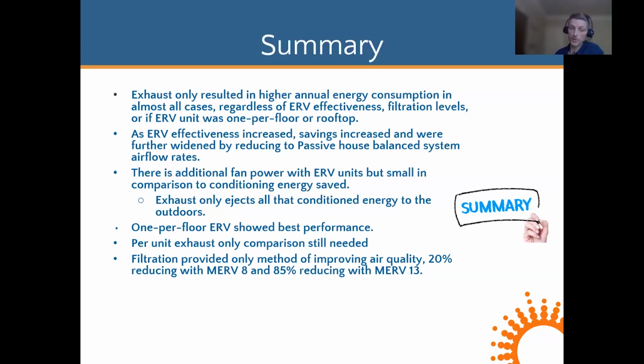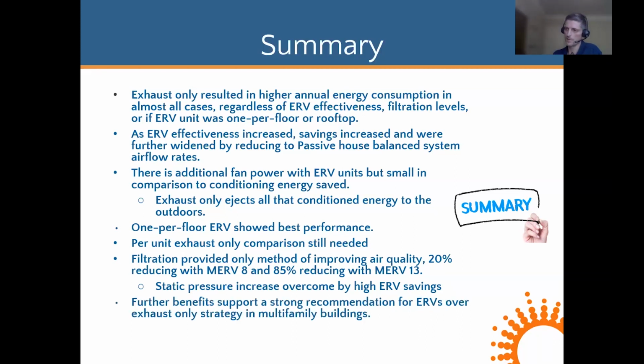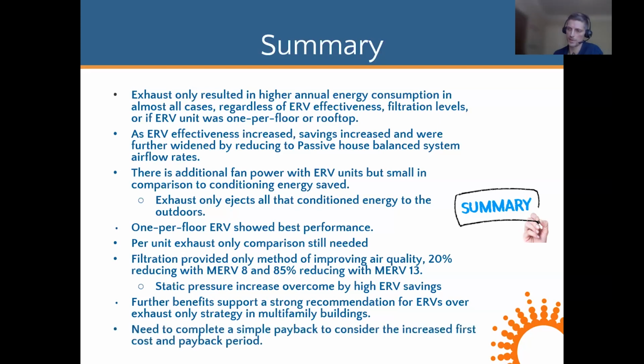Filtration provided our only method of improving air quality: 20% reduction for MERV 8s, 85% for MERV 13s. There was a static pressure increase to overcome, but this was overcome by the total ERV savings. And we saw further benefits to strongly recommend ERVs over exhaust-only strategy in multifamily buildings. Would like to add a simple payback to this analysis to consider the increased first cost and the payback period.